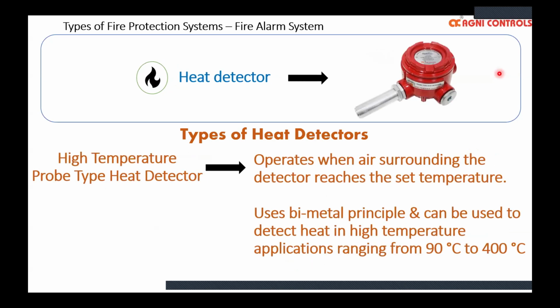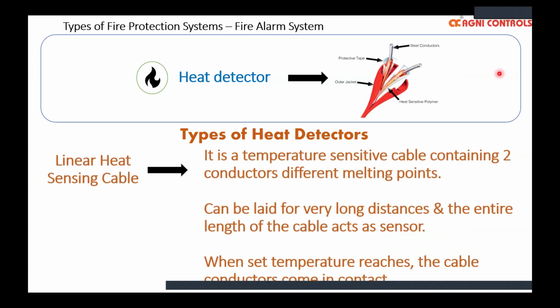High temperature probe type heat detector. This is also a fixed type of heat detector, but it contains no electronic components and is a purely bimetal type of sensor. So it can be used in very high temperature areas, from 90 degrees up to 400 degrees Celsius. And we have the linear heat sensing cable, a cable with different conductors having a special polymer coating, and based on the set temperature, the conductors come in contact and give an alarm. There are different types of LHS cables available in the market, including fiber optics, but we are not going into that right now.